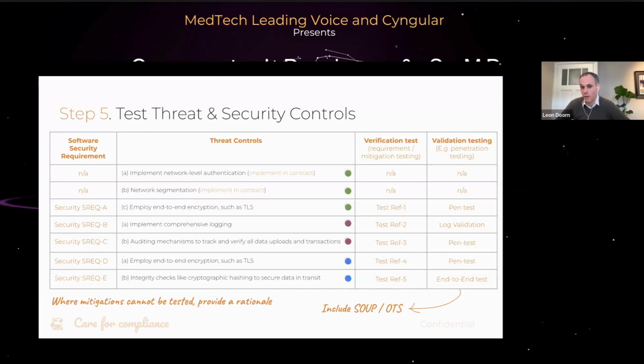And I think you just answered the other question, which was, does it mean that we need to do a separate cybersecurity risk analysis and medical device risk analysis following ISO 14971? Exactly. So this is precisely what the FDA is asking for, that you do a separate risk assessment approach for your cybersecurity risk management. And this is going to be a deliverable within your eSTAR. And literally, you cannot complete your eSTAR without having this deliverable done. So this is going to be a mandatory item from the FDA.